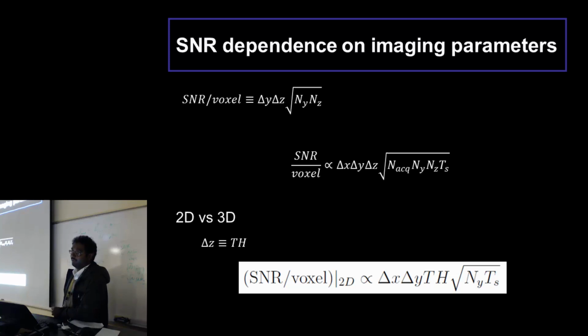So that would change your bandwidth. In other words, you want to change your bandwidth to keep your signal to noise ratio the same, or you could increase or decrease your matrix size, changing nothing else: reduce field of view and decrease matrix size. Then your voxel size remains the same, then your SNR is going to remain the same.